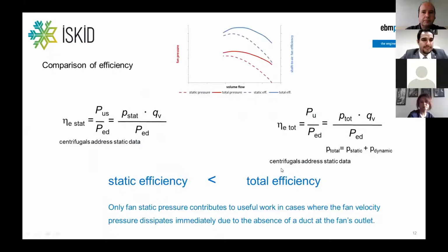And there are differences when looking into the definition of efficiency. Here on the top, you can see the fan curve. It's the same fan, but one refers to the static pressure, which is the dotted line, and this curve refers to the fan total pressure. This also has an effect on the efficiency. So this is the total efficiency, and this is the static efficiency. The total efficiency is always higher than the static efficiency.